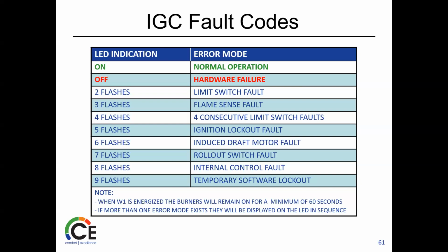All right. Just a note there, when W1 energizes, the burner will remain on for a minimum of 60 seconds. If more than one error mode exists, they'll be displayed in sequence. So if it has a 4 and a 7, you're going to see 4 flashes first, then 7, and then it reverts back and forth.